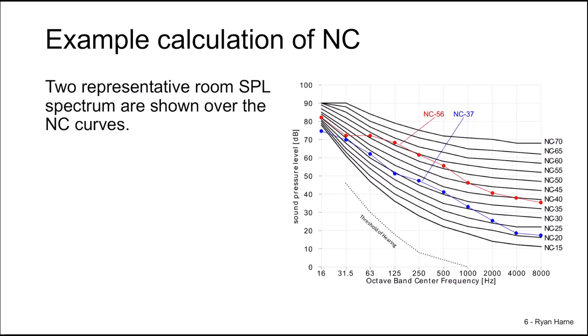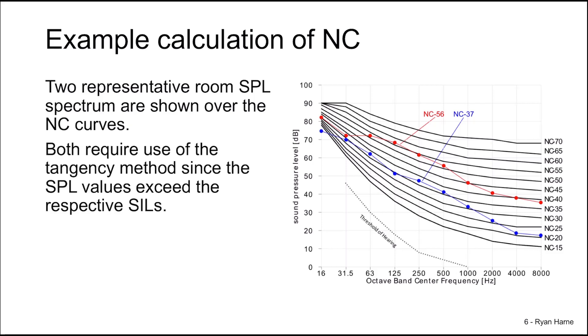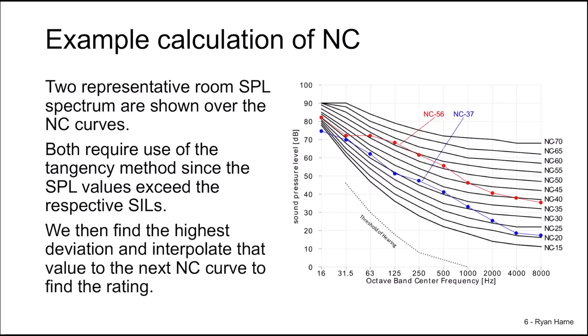Two representative room SPL spectra are shown in the NC curve plot here. One curve is shown in red and the other is shown in blue, along with our NC curves. Both require the use of the tangency method since their SPL values exceed the respective SILs. We then compute the highest deviation for each curve. For instance, the curve of data in red exceeds the NC 55 curve, and it exceeds it most right here. We then interpolate from NC curve 55 to NC 60, and we determine that this is going to be rated as NC 56, since it exceeds it by about one decibel over the 55 rating.